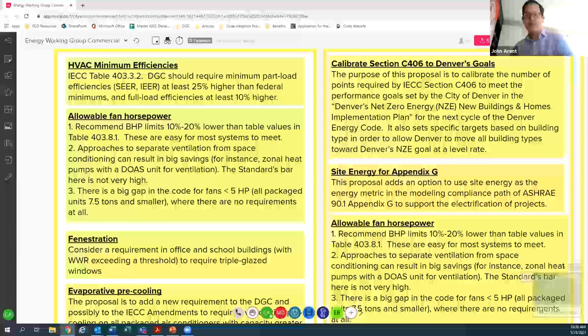And then finally, number 3 here, there's a bit of a gap in the code in most codes, including our code here in California, where there's no specific or explicit requirement for fan power for fans used in smaller systems. So for fans with a total system horsepower of less than 5 horsepower, there's no fan power requirement. So there could be some opportunities to set limits there.